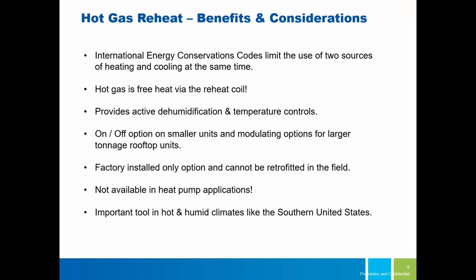So this is a strategy that does allow you to do active dehumidification and some temperature control. It's obviously not perfect, like a traditional chilled water option. And then I just noted here that for smaller units, you usually have an on-off option. If you get into larger tonnage units, you're going to have a traditional modulating option, which some people really like. For certain applications, modulating is something that might be important.